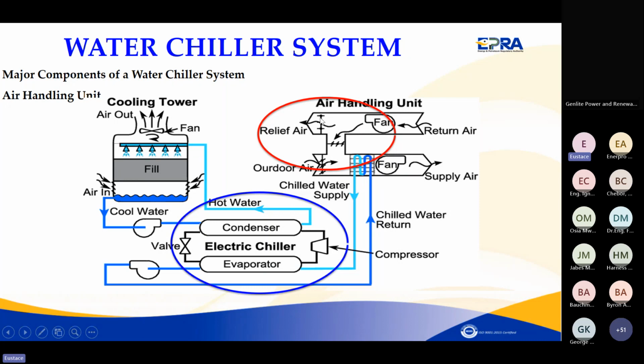But as I said, in operation theaters, this part is not there. You close this one completely, and once the air goes in, it goes out. But in areas like data centers, like halls, you can recirculate the air. In some cases, if you find that the conditions of the outdoors are below the room which is being cooled, you can switch off the chiller and run the pump alone. Or there is a way you can connect the cooling tower to the evaporator cycle and supply water without running the compressors of the chillers, because they are the main energy consumers.